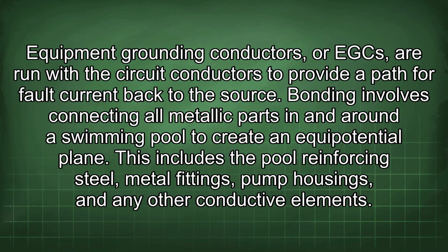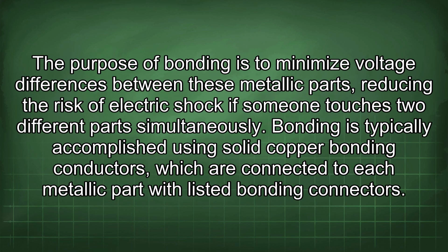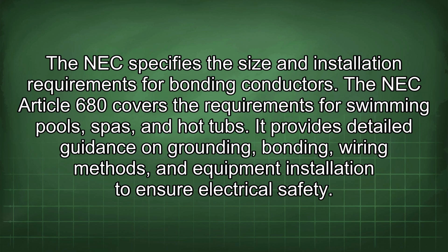Bonding involves connecting all metallic parts in and around a swimming pool to create an equipotential plane. This includes the pool reinforcing steel, metal fittings, pump housings, and any other conductive elements. The purpose of bonding is to minimize voltage differences between these metallic parts, reducing the risk of electric shock if someone touches two different parts simultaneously. Bonding is typically accomplished using solid copper bonding conductors, which are connected to each metallic part with listed bonding connectors. The NEC specifies the size and installation requirements for bonding conductors.